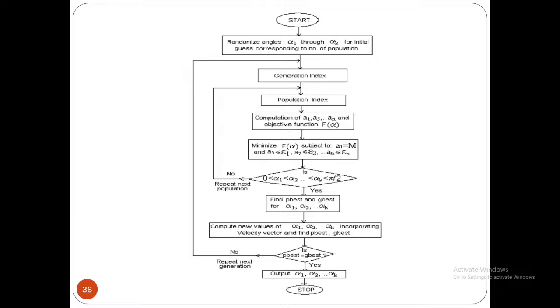So whenever it is coming to less than 5%, then you are accepting that value, subject to condition that the individual harmonics, you have already put that constant, it will not be more than 3%. Individual harmonics should not be more than 3%. So you have put that condition constant and alpha should be between 0 and 90 degree.